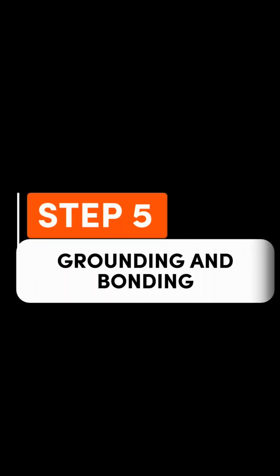Step 5: grounding and bonding. This is one of the most common reasons I fail an inspection. Always ensure a correct ground for your equipment — your control panel, your electrical motor, whatever applies — it has to be grounded properly, with the correct rod, cable, wire gauge and size. It has to be done correctly, because it's important: it's protection for the people who use the equipment, and also protection for the equipment itself. Step 6: label everything.